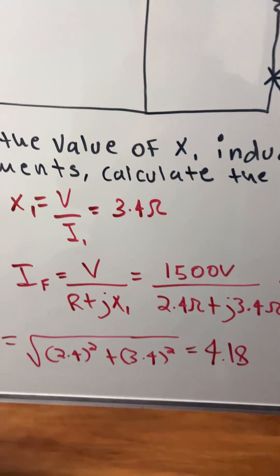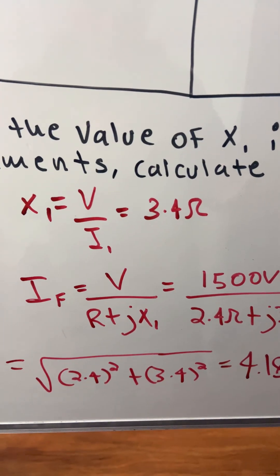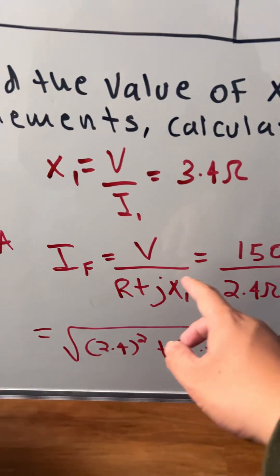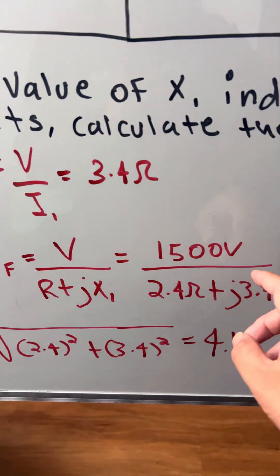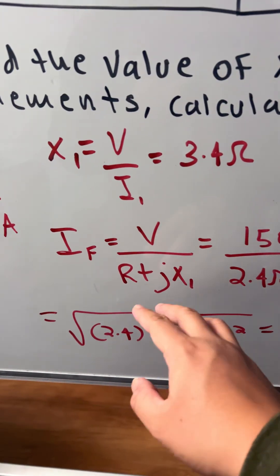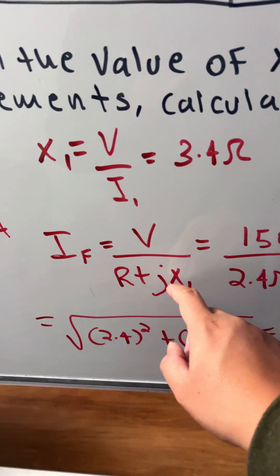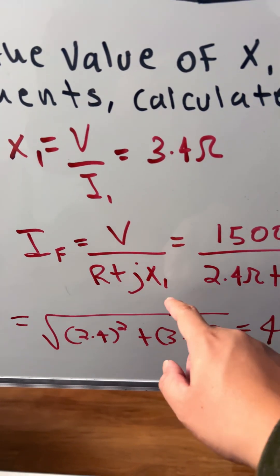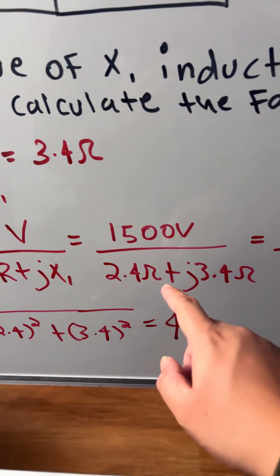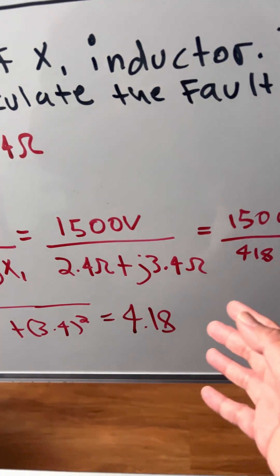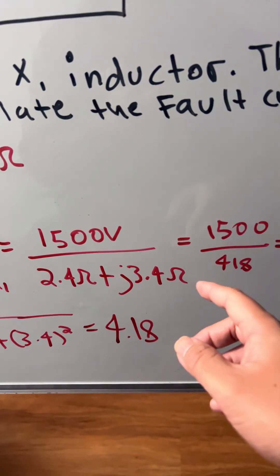Now we're going to solve for the fault current. So we have the voltage 1500, and then we have the impedances: the resistance plus the inductance, so 2.4 ohms plus j3.4 ohms.